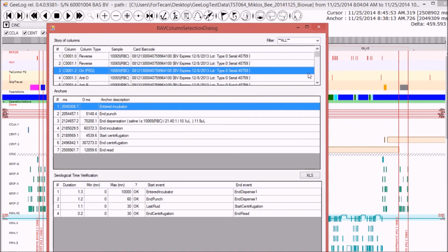The aim of this tool is to make a validation of the analysis, so verify that a number of specific moments called anchors, for instance the dispensation of a volume of reagent or sample into a column, which is one of these little vials that contain reagents, or the fact that one of these consumables has been put into the centrifuge, match to the prescribed assay specifications that are included in a specific file.